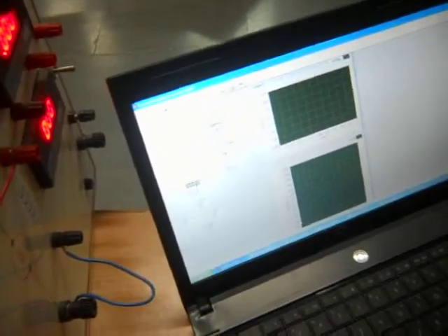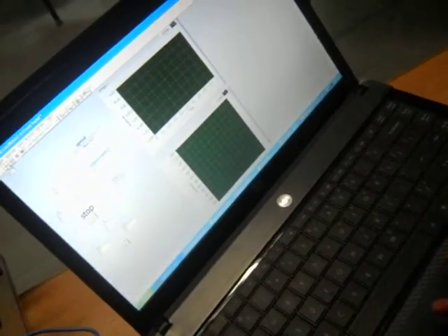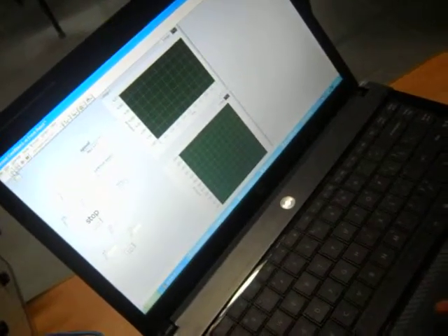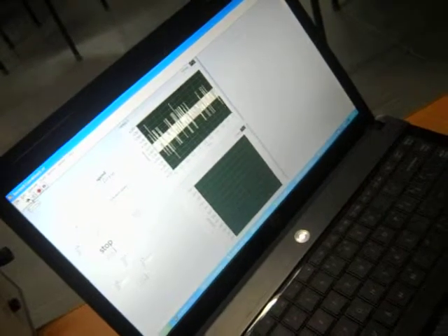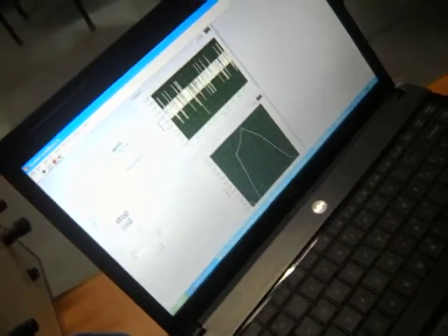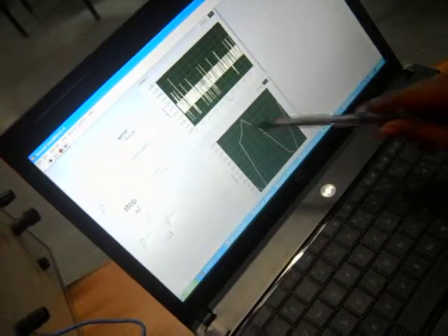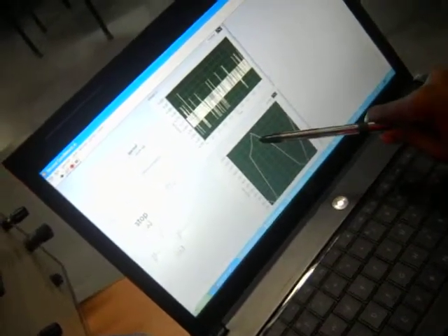So we start the second condition now. This is the same as the first condition, but the only difference is that in the first condition both the field and the armature are off, but here the field supply is retained, and only the armature supply is made off. So as usual, the motor is given a reference speed and it starts. Now after reaching the rated speed, you can see it's automatically being off. So only the armature is being off, the field is still there. So you can see the retardation clearly. That is the retardation which is seen.